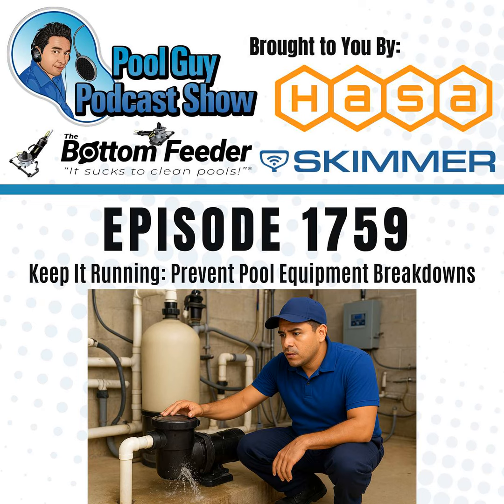But over time, as the motor gets older, as it runs hot, those pump seals will fail, and you're going to notice a little drip leak right underneath the motor. You're thinking maybe that the water's coming out of the motor, but it's not. It's coming out of the pump seal, and the pump seal is there to keep the water, basically, the wet part of it, out of the motor. And so when that fails, water is going to drip from underneath the pump or underneath the motor itself, and that needs to be replaced.